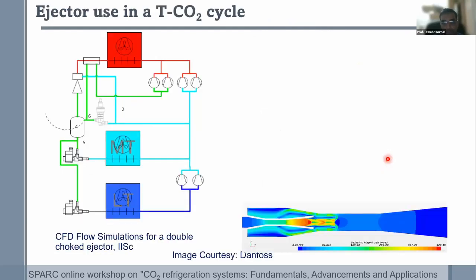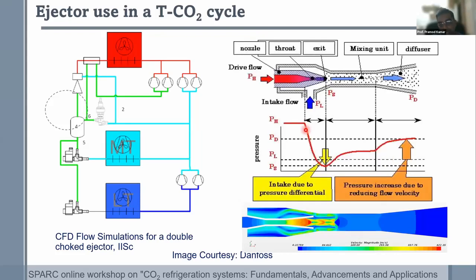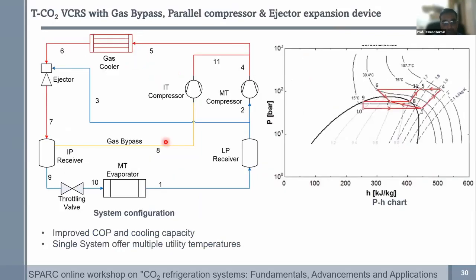Another thing: Dr. Pradeep Gupta will shortly give a detailed presentation on how an ejector works. But what an ejector means is that it is one of the devices to recover partially the energy from the high pressure stream discharging from the exit of the gas cooler, to lift the subcritical carbon dioxide discharge from the evaporator to an intermediate pressure and reduce the compressor work. This technology is now fairly matured. A lot of components and the cycle are available with most commercial manufacturers like Danfoss, Carel, etc. So all of this is pre-programmed. This shows a system with how an ejector is used.